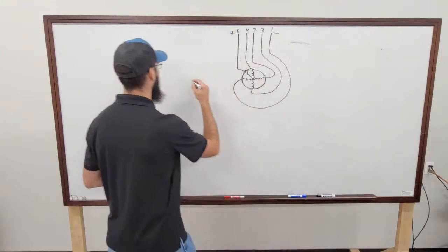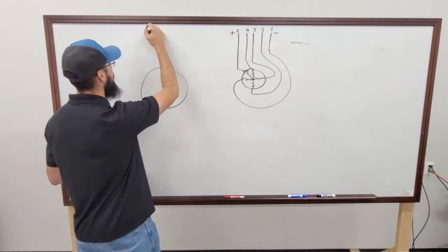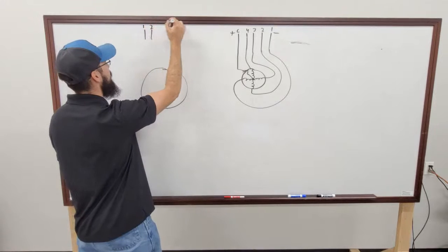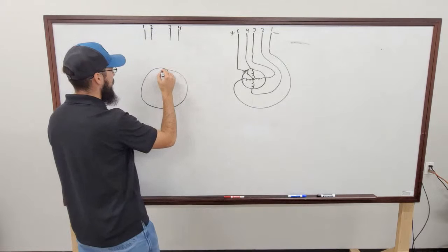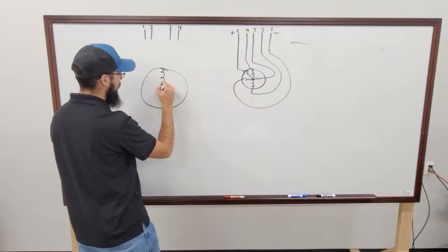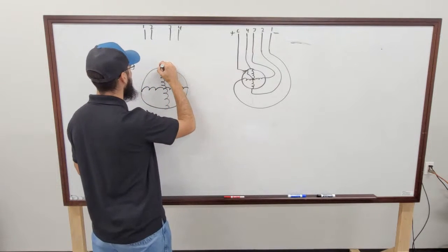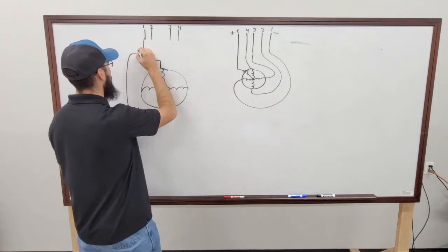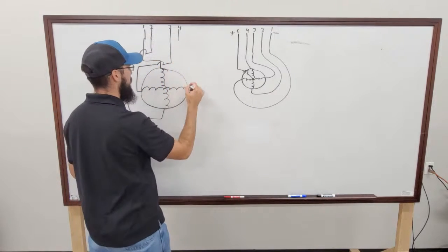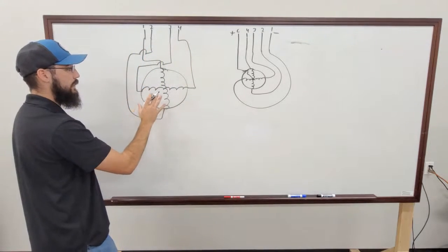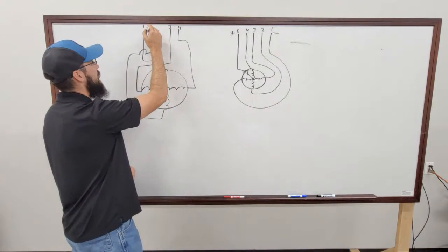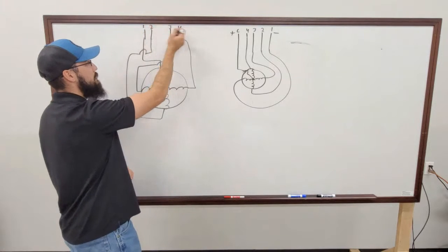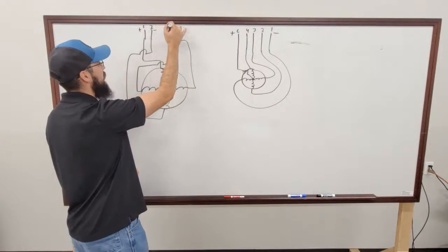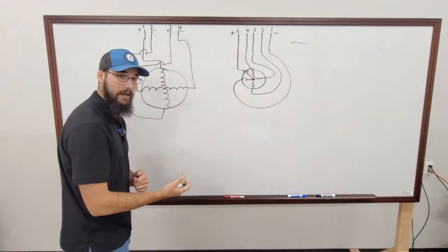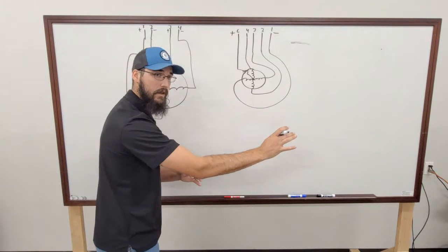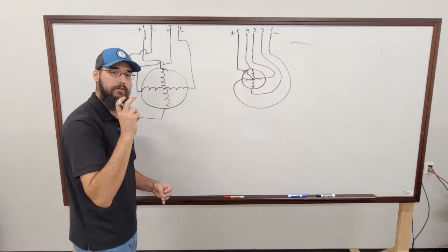So this is one line of thought. The other common line, it's a lot simpler in my opinion. You just have 4 wires. Each of these are tied together. So you'll have a 1, 2, 3, and 4. And then inside of this, this is by far not a nice drawing, but it gets the point across. You'll have 2 different sets of windings doing the exact same thing. We fire this, 1, 2, 1, 2, 1, 2. And each time we cycle between the windings, in this case, 1 would be positive, 2 would be negative, 3 would be positive, 4 would be the negative in polarity. Every time we cycle that, we're taking a step. And then we just reverse polarity and cycle it right back out to drive it the opposite direction.